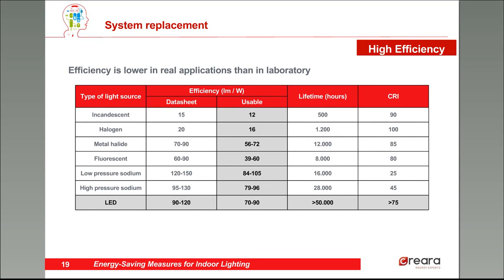This table shows the differences between laboratory conditions and real applications. Efficiency is always lower in the real world — in LEDs and also in conventional lighting. For fluorescent lamps, the datasheet efficiency is 60 to 90 lumens per watt, but the usable efficiency is 39 to 60 lumens per watt. In LEDs, the laboratory efficiency is from 90 to 120 lumens per watt, and the real usable efficiency is from 70 to 90 lumens per watt.